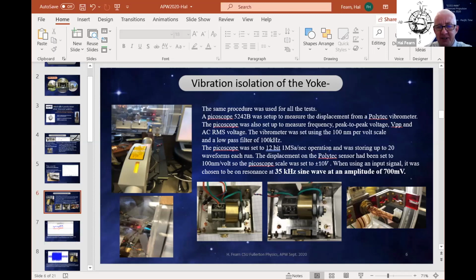So this information is just telling you how I set up the vibrometer. It was on a 100 nanometer per volt scale. I had it on plus or minus 10 volts. I was running 35 kilohertz, which was the on resonance of this device. So I was actually running this thing on resonance using a picoscope at 35 kilohertz, and the input was 700 millivolts. And so let's see what happened when I did that.